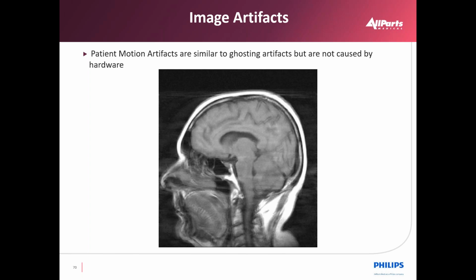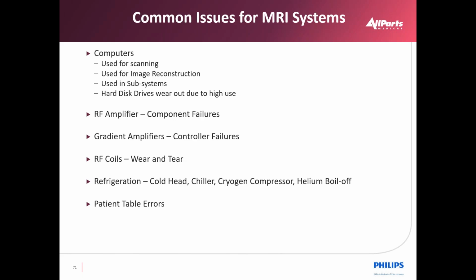Patient motion artifacts are similar to ghosting artifacts, but are not caused by hardware. As the name implies, they are caused by the patient moving while being scanned. Common failure items for MRI include host computers or reconstruction computers, RF amplifiers, gradient amplifiers, RF coils, cold head and cold head compressor, which is part of the refrigeration section, and patient table issues.